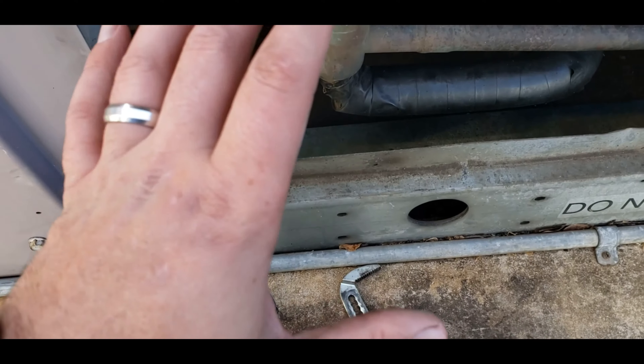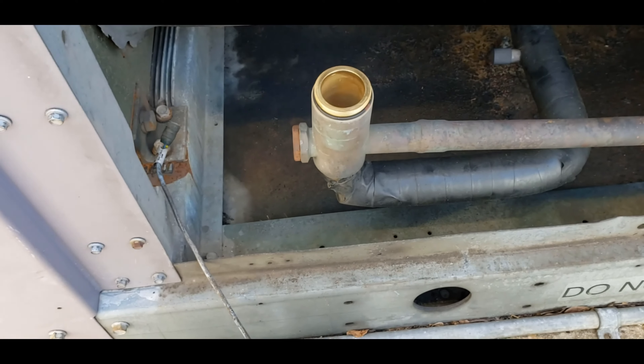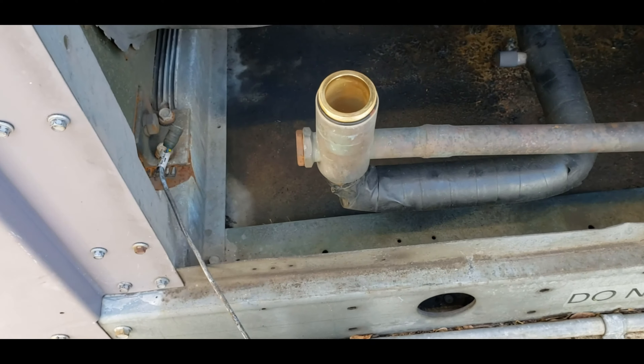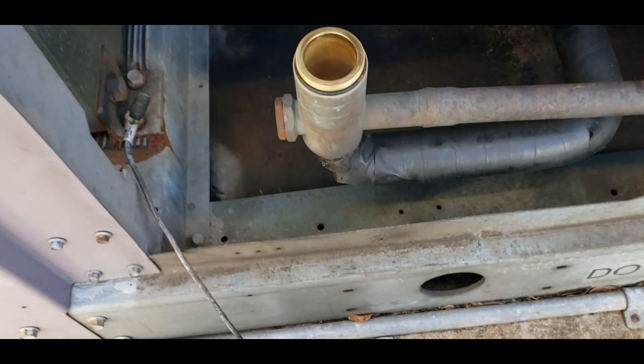So I've got a new actuator head. One of the things I'm looking for is I'm going to check for any damage. I want to make sure I clean this up as much as possible inside. Instead of sweating this whole body out, I'm going to just replace this head. The body so far — I don't see any obvious damage.